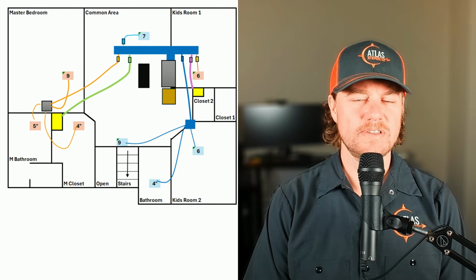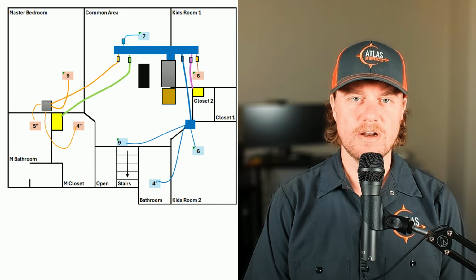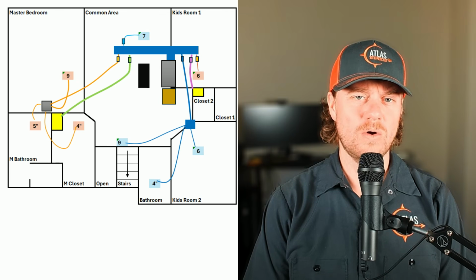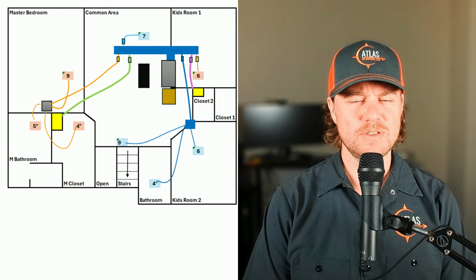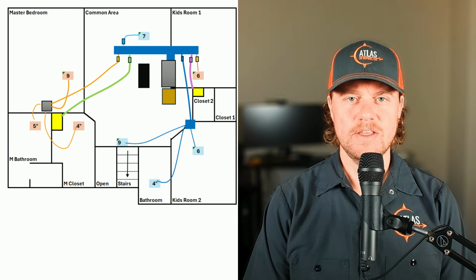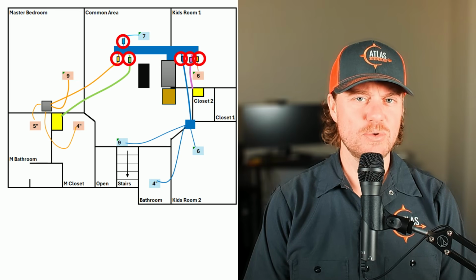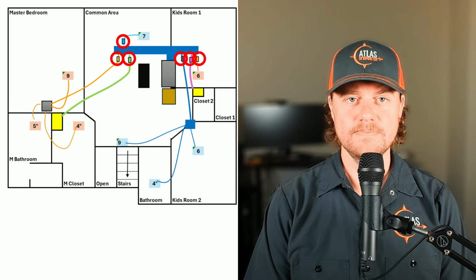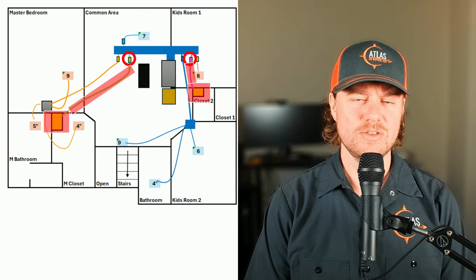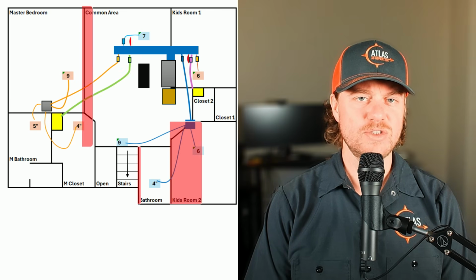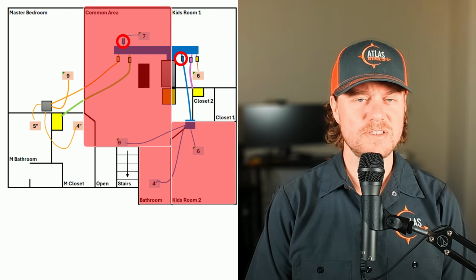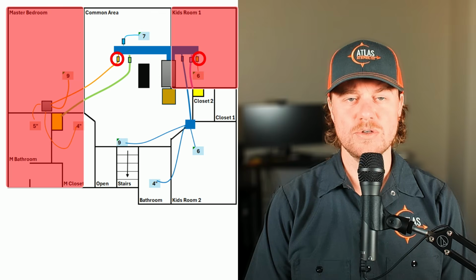Here is the end results of my zoning system after all the tweaks and modifications. The design does look a little wonky, but we are very limited in options due to how tight my attic was. You can see that I have a total of 6 zoning dampers. Each damper is paired with another one. For example, these 2 here are going down into a chase feeding my downstairs. These 2 are feeding the upstairs common area and my son's room. And these are feeding the master bedroom and my daughter's room.